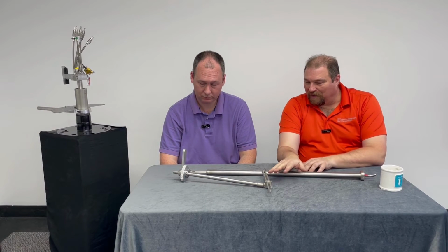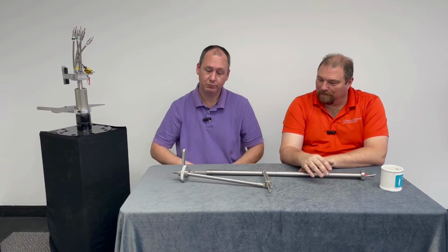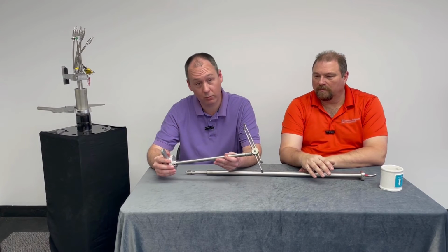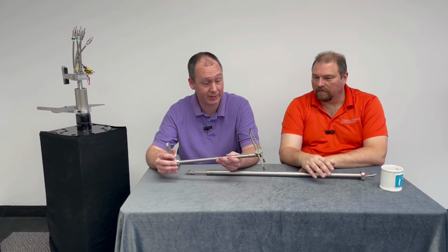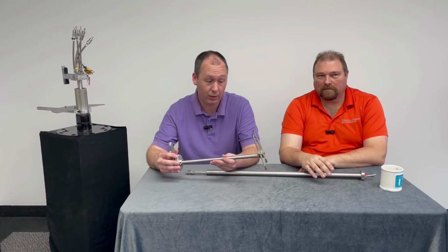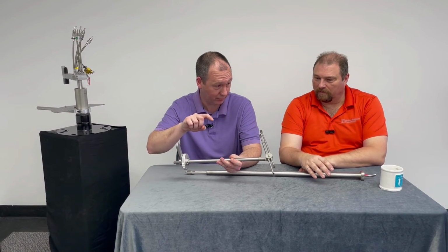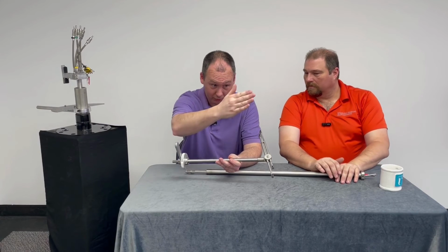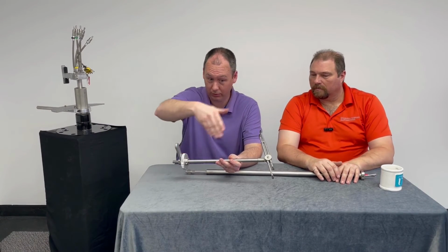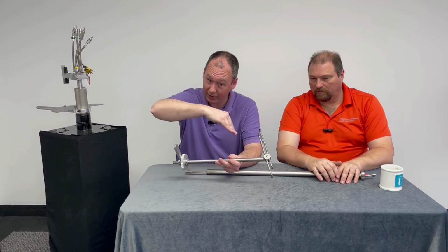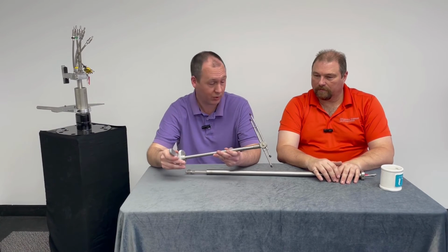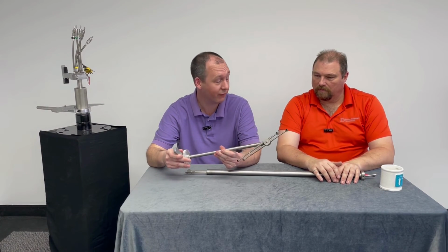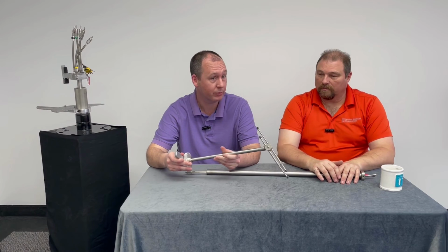Fascinating. Well, I know that there's other methods and other pieces of equipment for sampling coal isokinetically. What are the advantages of, say, this method compared to the other methods? Yeah, that's a great question, Kevin. So with, in particular, the ASME PTC 4.2 method, you just have a probe with a single nozzle, and maybe you have one test port, maybe you have two, but either way, you're only getting maybe one line of data or maybe two lines of data across that coal pipe. Whereas with this probe, you're really covering the entire cross-section by spinning it around.